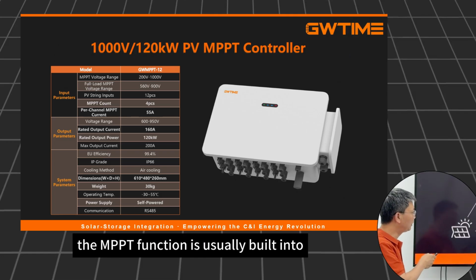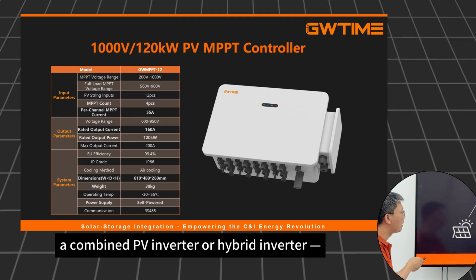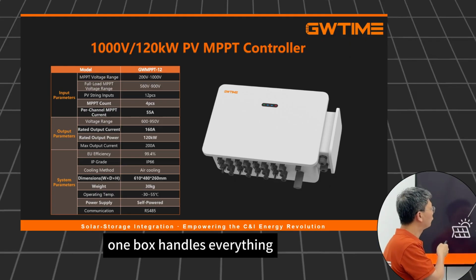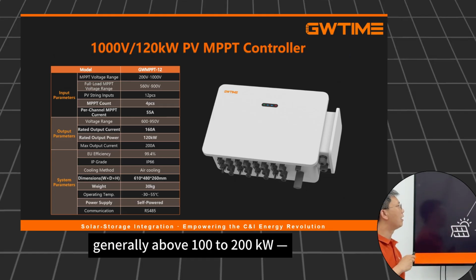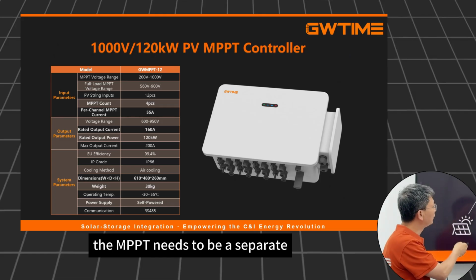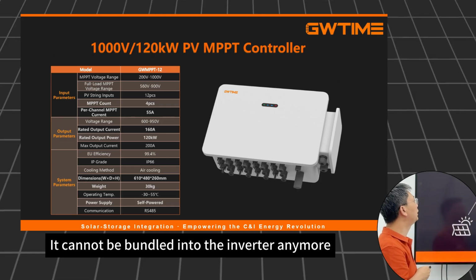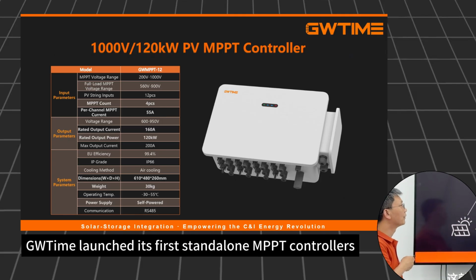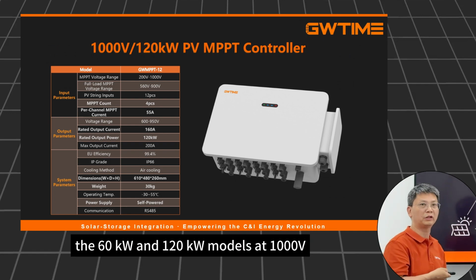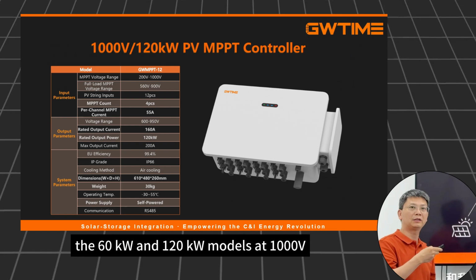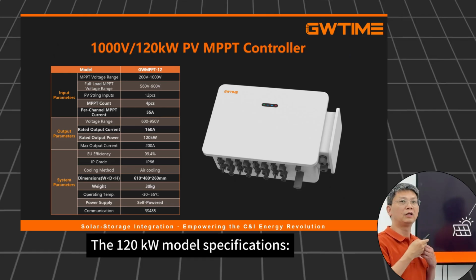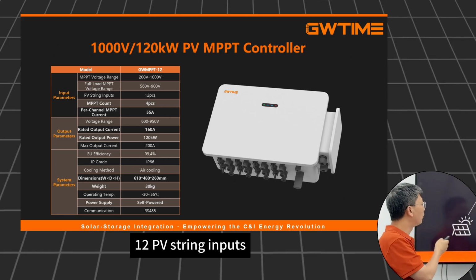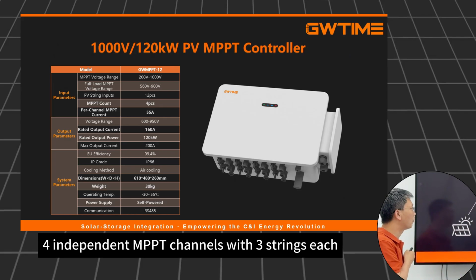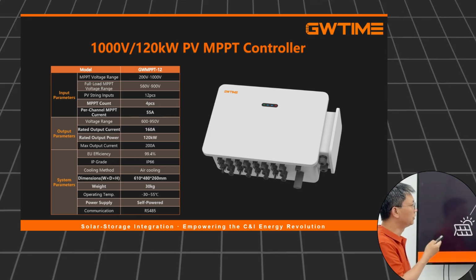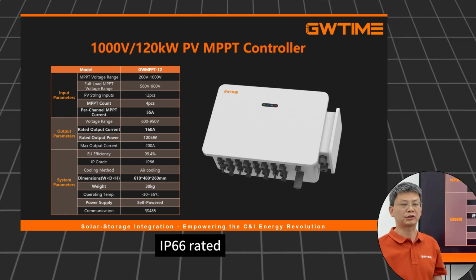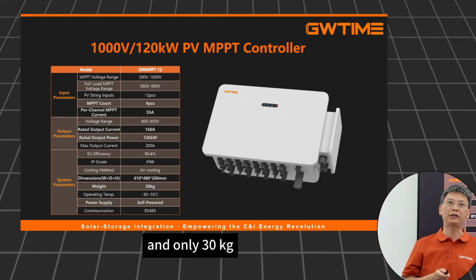For small systems, the MPPT function is usually built into a combined PV inverter or hybrid inverter. One box handles everything. For larger systems, generally above 100 to 200 kilowatts, the MPPT needs to be a separate standalone unit. It cannot be bundled into the inverter anymore. GWTime launched its first standalone MPPT controllers in 2025, the 60 kilowatt and 120 kilowatt models at 1000 volts. The 120 kilowatt model specifications: 12 PV string inputs, 4 independent MPPT channels with 3 strings each, 55 amps per channel, 120 kilowatts total output, IP66 rated, air-cooled, and only 30 kilograms.